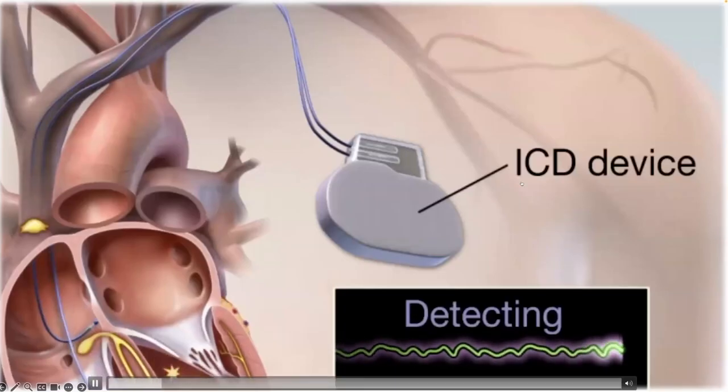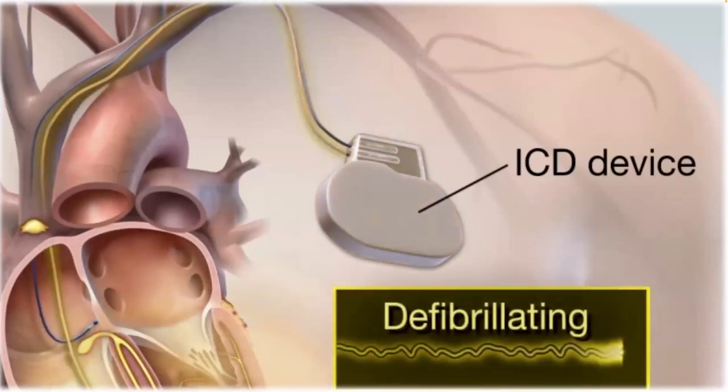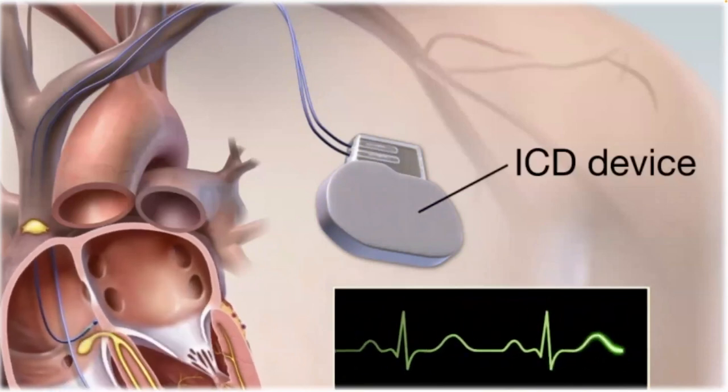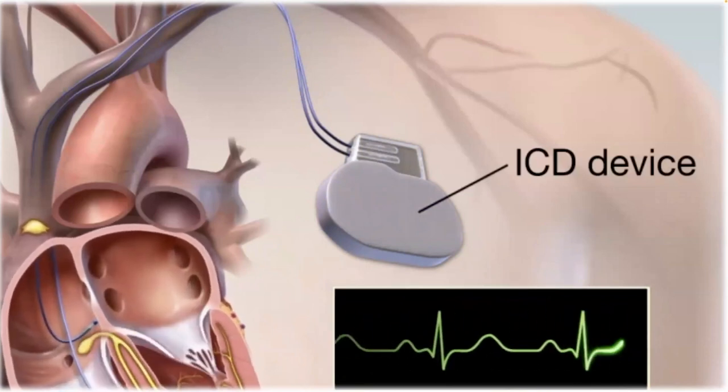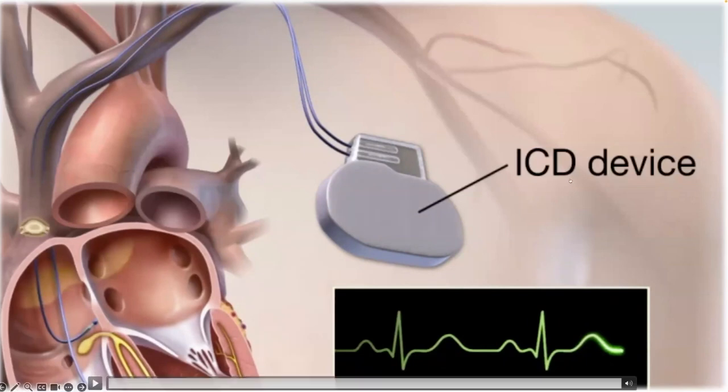As you can see, this is the process of how implantable cardioverter defibrillator devices work, and we call them ICD devices. They keep an eye on our heartbeat using a signal called the electrogram signal. If the ICD notices the heart is beating the wrong way, it will send a shock to get the heart back to its normal rhythm.